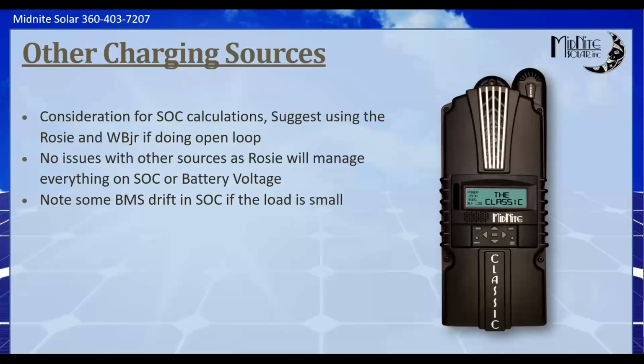Consideration for how you're doing your state of charge calculations. If there's a Rosie in the system, which there probably is if we're talking about grid curtailment using the Rosie, and you're not doing closed loop, I would suggest letting the Rosie do the state of charge using Whiz-Bang Jr. If you're doing closed loop, then of course the battery provides that state of charge. If you're not comfortable with the state of charge, these settings can also be programmed to run on battery voltage, which is a little trickier on lithium, but it's still doable, and sometimes can actually be a benefit.